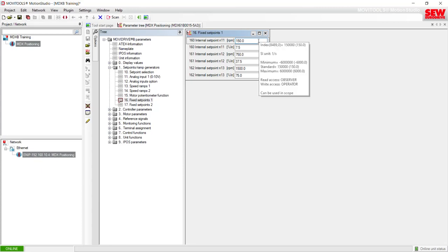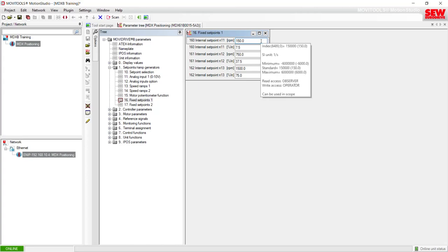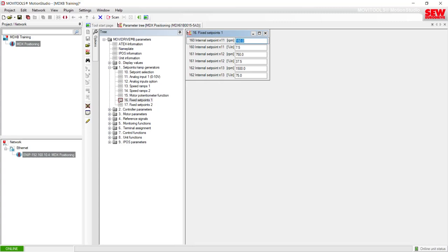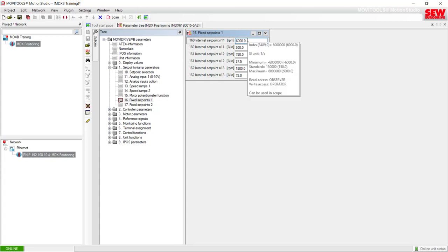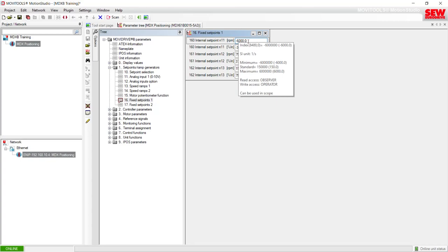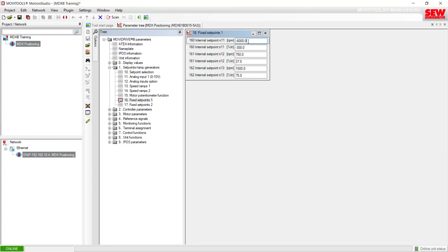In the center of that pop-up, the minimum value is minus 6000, the standard value is 150 — that's the default when you delivery-state the motor drive — and the maximum value is 6000. So if I tried to enter 6001, it will take it back to 6000 because that's the maximum, and the same applies in the negative direction — minus 6001 would be clamped to minus 6000. But that would be way too high for the type of motor I have connected, so it will be on me to make sure I don't enter a value that exceeds the physical motor capability.